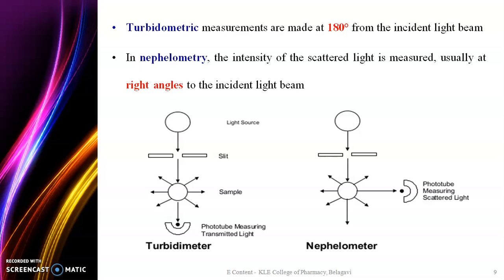Turbidimetry measurements are made at 180 degrees from the incident light beam. Whatever light is transmitted by the sample will be measured at 180 degrees in case of a turbidimeter. In Nephelometry the photo tube is placed exactly at right angle or 90 degrees to the sample holder, measuring the scattered light.